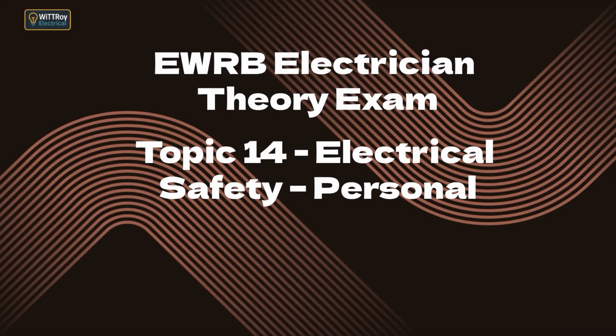14.2g Detail written isolation procedures. Written isolation procedures describe identifying all energy sources, isolating and locking off, applying tags, testing dead, carrying out the work, removing locks, and restoring power safely. These procedures support legal compliance and ensure consistent safe practice.